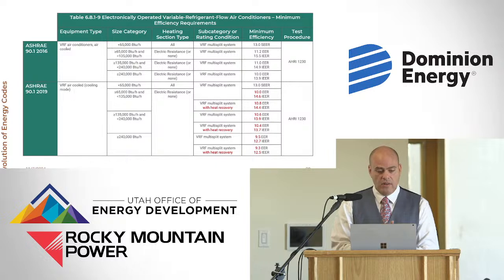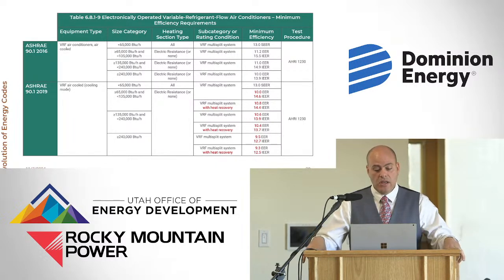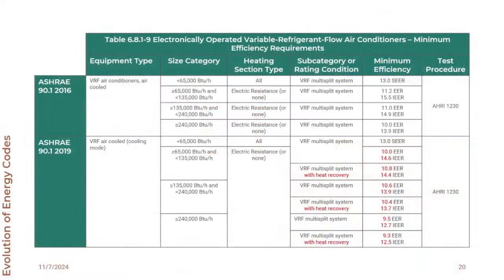So again, before we dive into these things, I want to explain some of the acronyms. EER is energy efficiency ratio. Good, it's large enough for you to see it. So the higher the EER, the more efficient the HVAC system. IEER is integrated energy efficiency ratio. Again, the higher the number, the more efficient the system. However, EER focuses on the mechanical equipment's efficiency at peak load, and IEER focuses on mechanical efficiency at part loads, at different part loads.